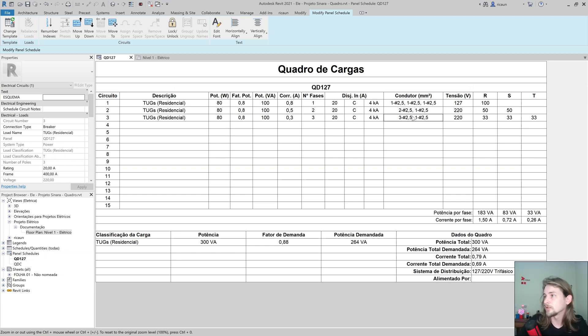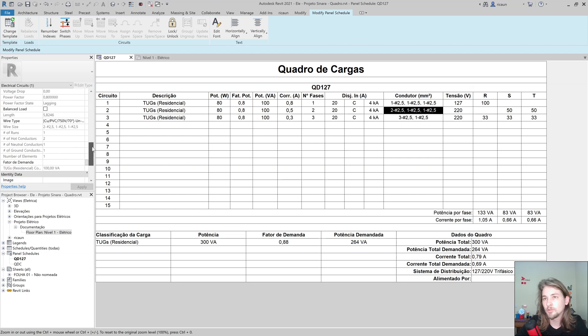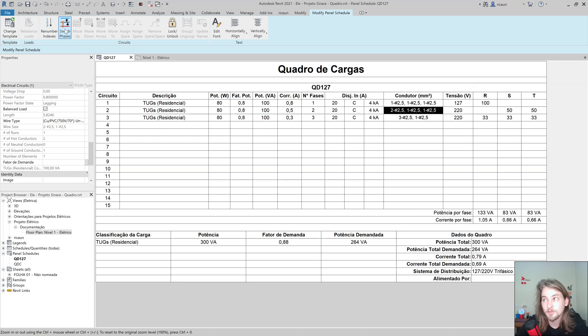That's what I want, but if I change the phase in this specific circuit with two hot wires, look what happened. For some reason, Revit adds a neutral. And this circuit is now not balanced — that's why it put a neutral. And if I switch again, not balanced, and with this configuration it's balanced again. For some reason, this is what happened.